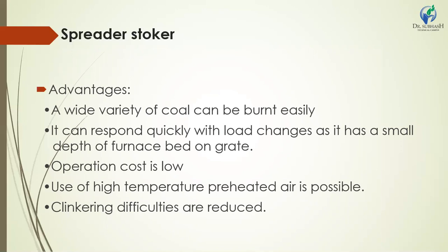Clinker problem is reduced due to ash under firing cooled incoming air. Its operating cost is very low, so maintenance cost is low. Use of high temperature, preheated air is also possible. Volatile matter is easily burned. Fire arches are not required. The thin fuel bed on the grate is helpful in meeting fluctuating loads.